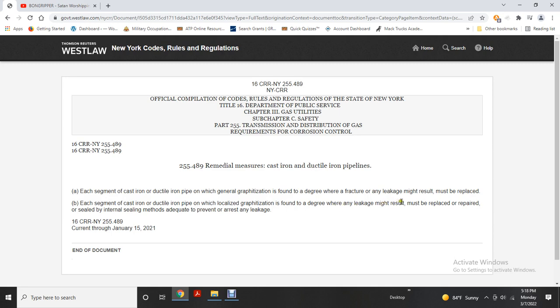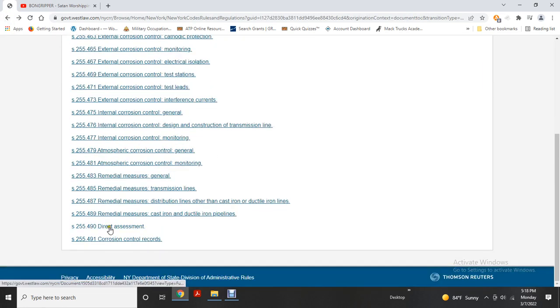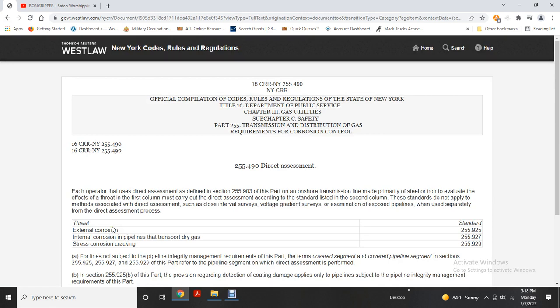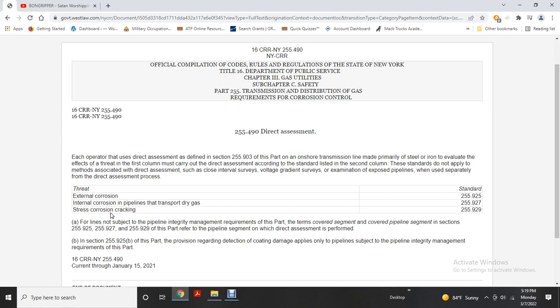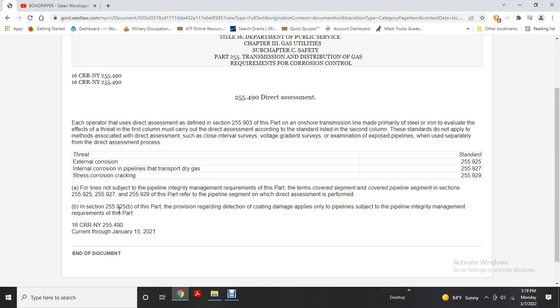Adequate internal sealing methods must be used to prevent and arrest any leakage. For direct assessment, as defined in Section 255.903, onshore transmission lines made primarily of steel or iron must evaluate the threat of external corrosion according to the standard listed in the second column. If those standards do not apply, the operator must associate the direct assessment process with close-interval surveys, voltage gradient surveys, and examination methods. External corrosion direct assessment: 255.925; internal corrosion for pipelines transporting dry gas: 255.927; stress corrosion cracking: 255.929.